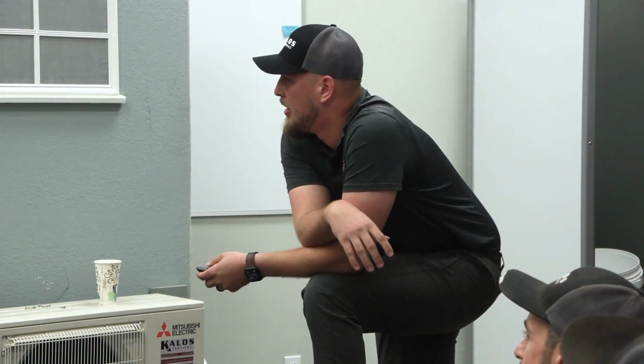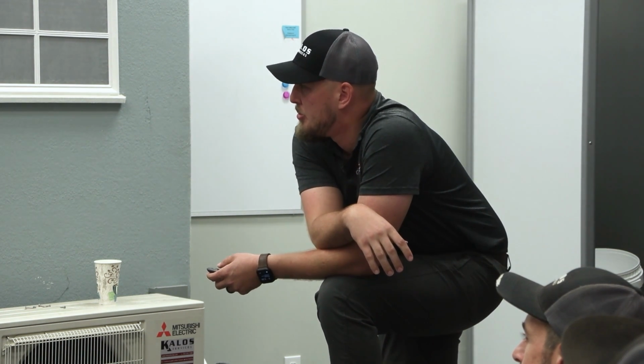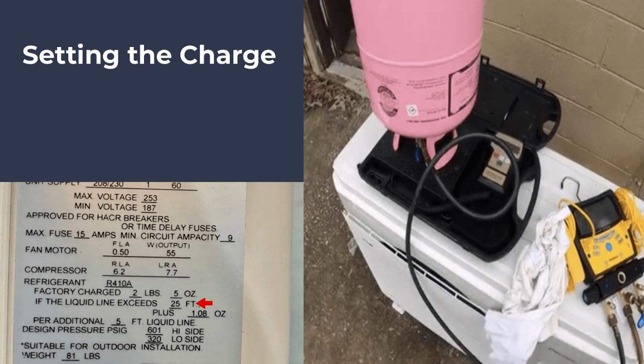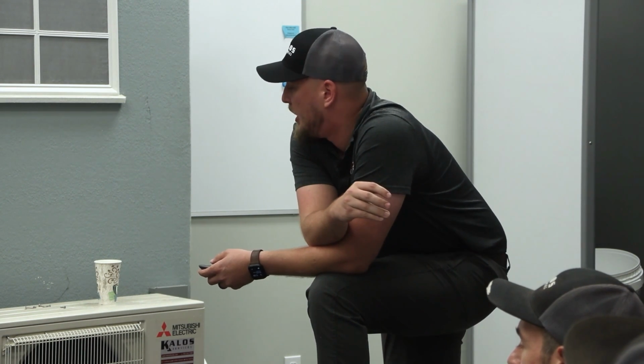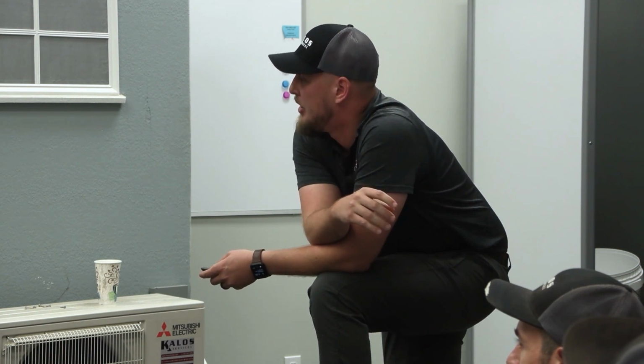As far as needing to add any refrigerant, it is stamped right on the data tag on how to do that. You can't go by subcool or by pressures usually. You do have to go by the line set length. So if we look at this data tag here, we can see if the liquid line exceeds 25 feet, we need to add 1.08 ounces of additional refrigerant for every 5 feet. So knowing how much line you're actually using is going to be important here.